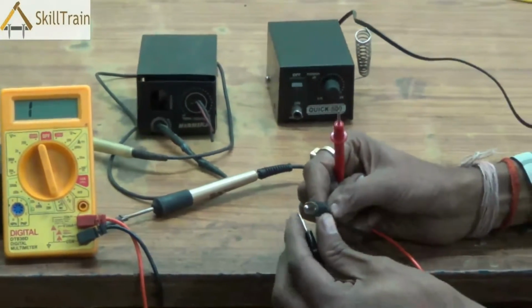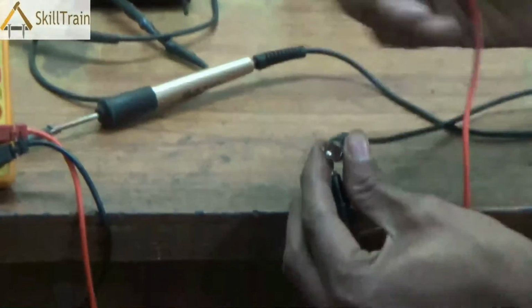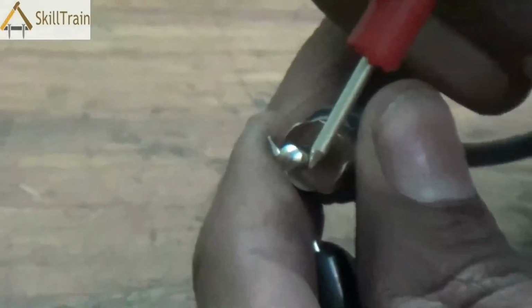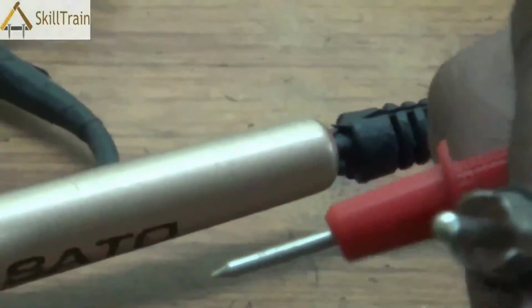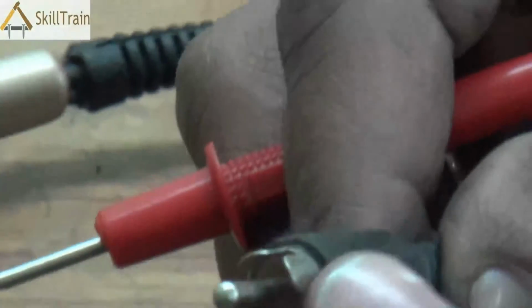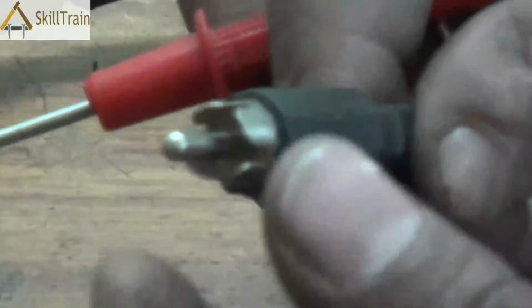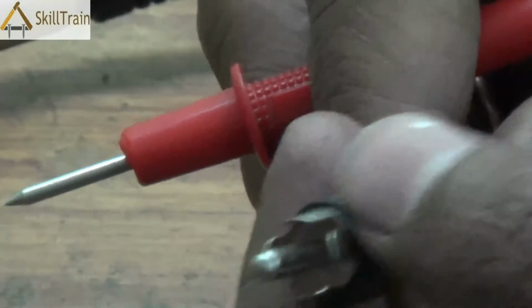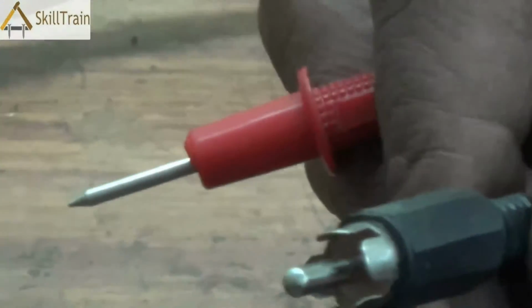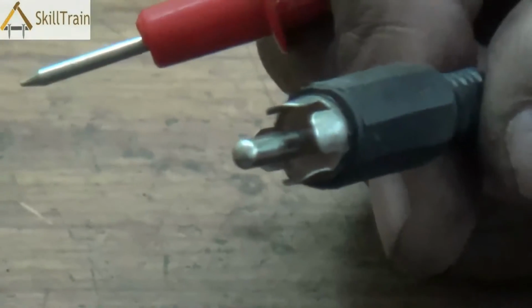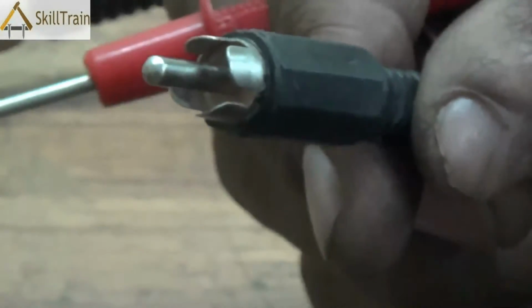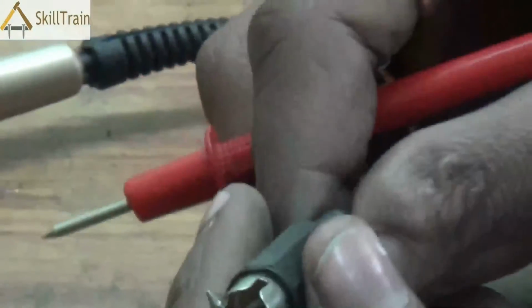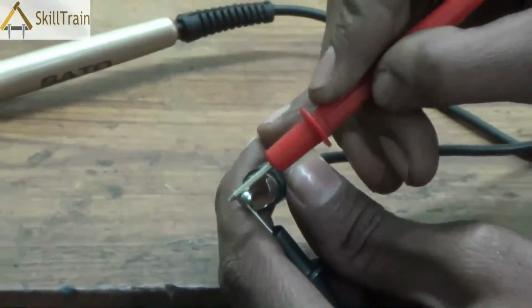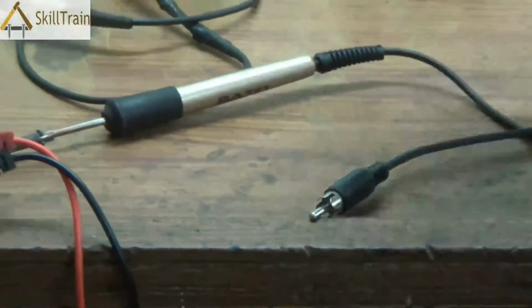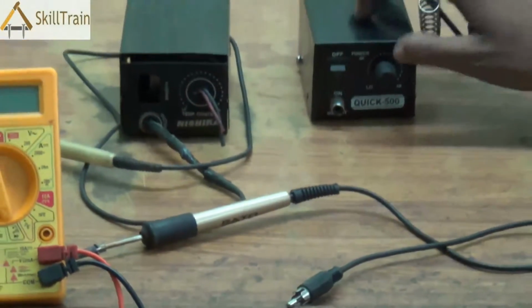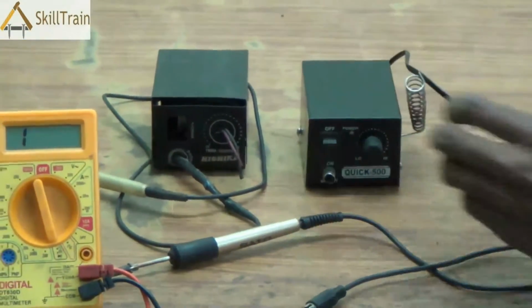Now, there are 2 points on the one end of the micro soldering iron. You place your tips on these 2 points, the outer one and the inner one, and once you place the 2 tips of the multimeter on this, if this entire wire is intact and the connection inside is intact, you will hear a beep. As you can see now, you will hear a beep. This means that the wire or the connection for this entire part is intact. So, the soldering iron and its connecting wires are intact.